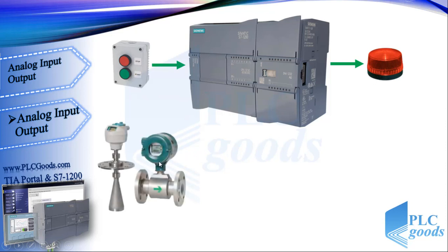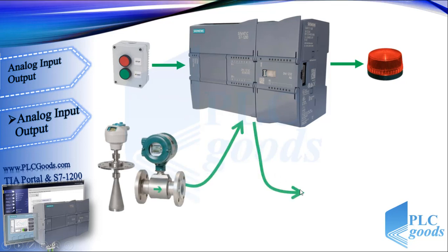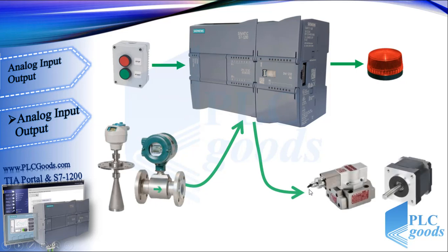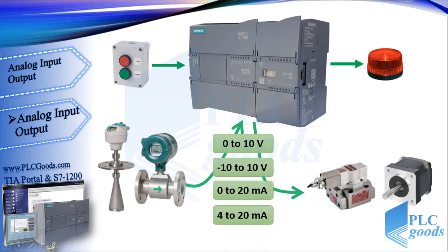On the other side, there are many devices such as level and flow meter transmitters, and also some actuators which use analog signals. For example, a voltage between 0 to 10 volt. Other basic signals are minus 10 to 10 volt, 0 to 20 milliampere, 4 to 20 milliampere, and other types. To store and use these signals in the PLC program we need more than 1 bit — usually 16 bits.